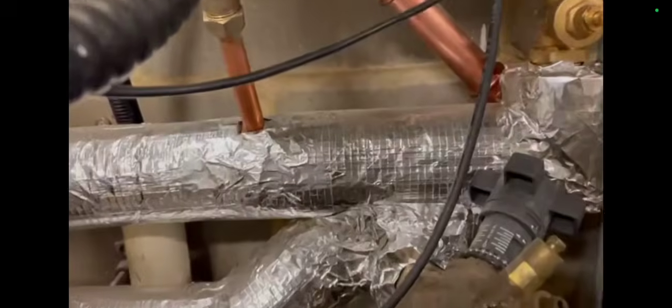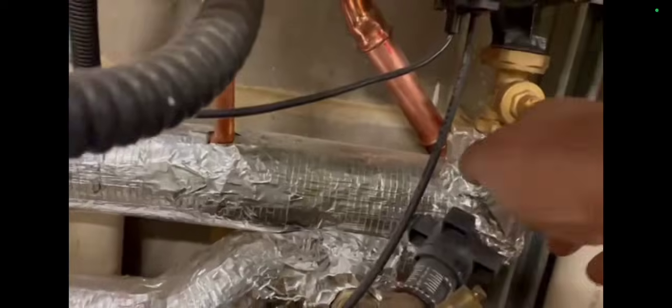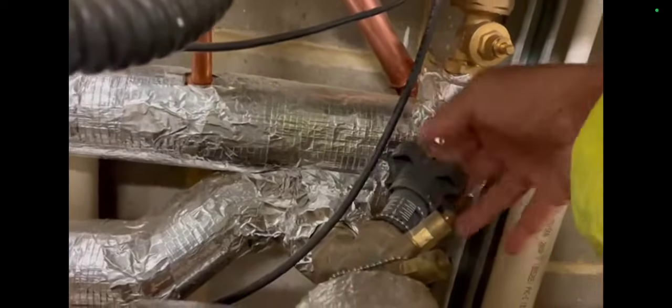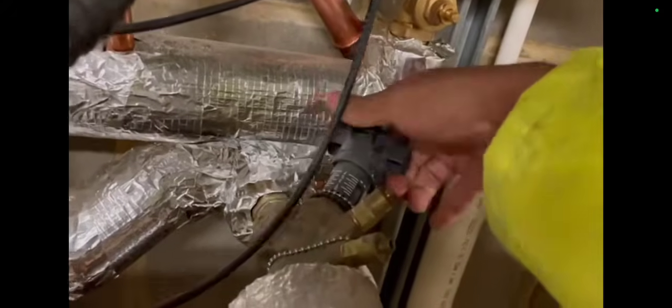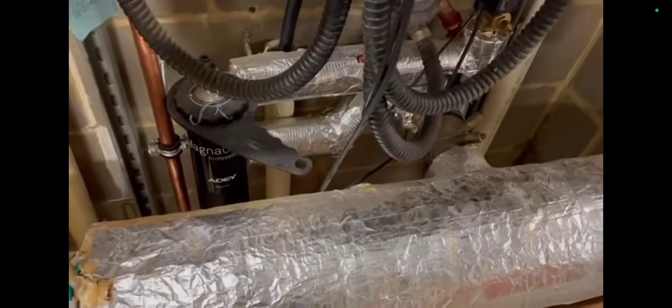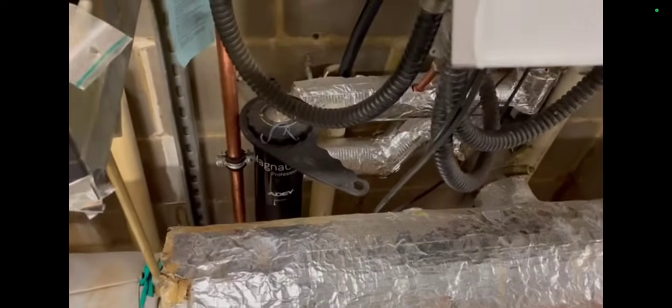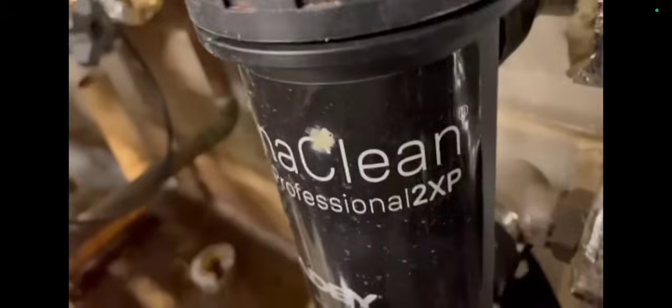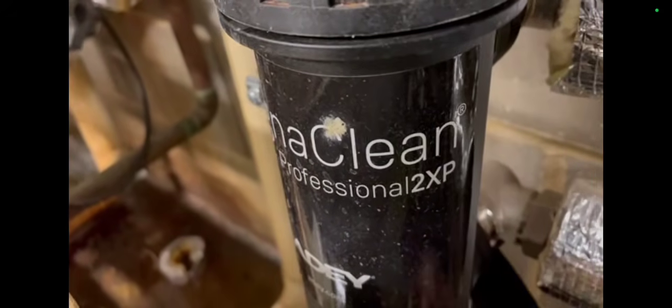You can see that isolation, that lever isolation valve was letting by. And then we have a commissioning valve here that needs isolating. So that should stop the water in the system. But just to be sure, I'm going to also isolate the Magna Clean's isolation valves if I can get to it. Yes, I could just about get to the one at the top. Lovely, got to that. And then the one at the bottom. Sorted.